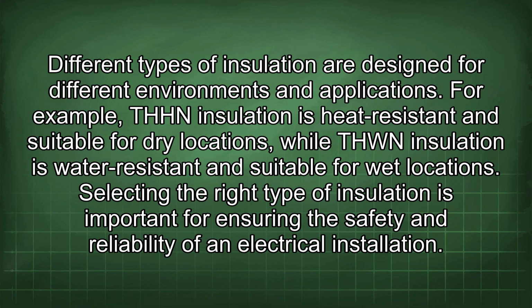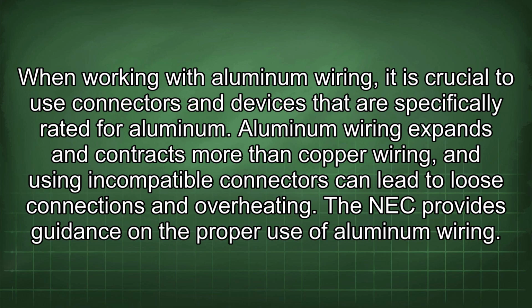For example, THHN insulation is heat resistant and suitable for dry locations, while THWN insulation is water resistant and suitable for wet locations. Selecting the right type of insulation is important for ensuring the safety and reliability of an electrical installation. When working with aluminum wiring, it is crucial to use connectors and devices that are specifically rated for aluminum. Aluminum wiring expands and contracts more than copper wiring, and using incompatible connectors can lead to loose connections and overheating. The NEC provides guidance on the proper use of aluminum wiring.